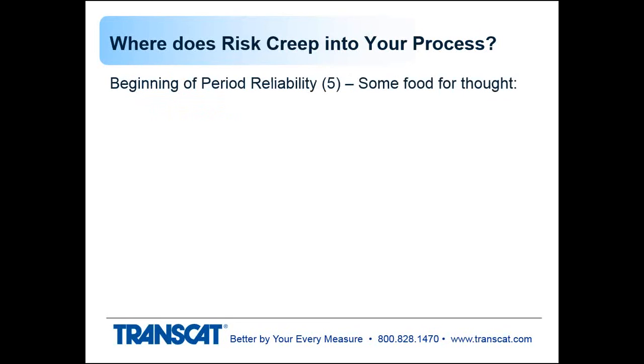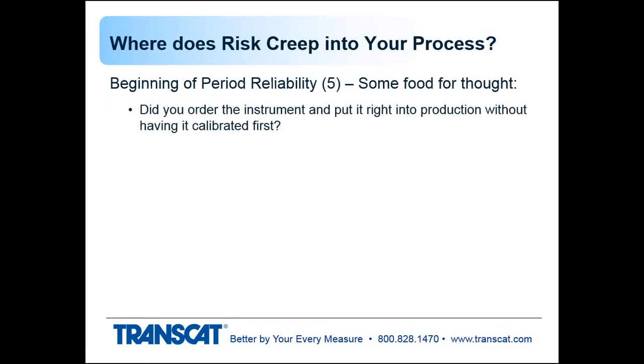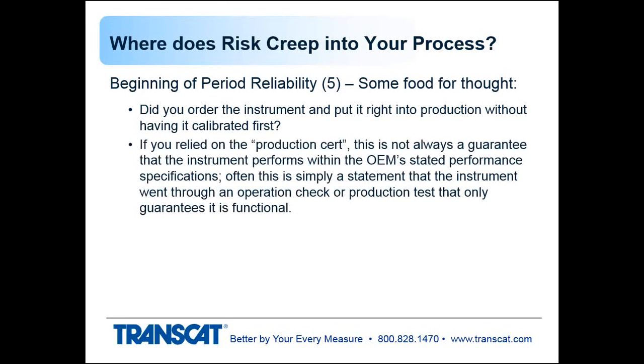Beginning of period reliability. Here are some things to think about. When you order an instrument, do you put it right in production without having it calibrated first? I've seen that happen. People use P cards and don't run it through the calibration system, or calibration is not aware of the newly purchased instrument, and the instrument is being used to make decisions. If you relied on the production certificate for calibration, that's not always a guarantee that the instrument is performing within the manufacturer's stated specs. Sometimes that's simply a statement that the instrument went through an operational check or a production test and guarantees that it's functional, not necessarily calibrated.